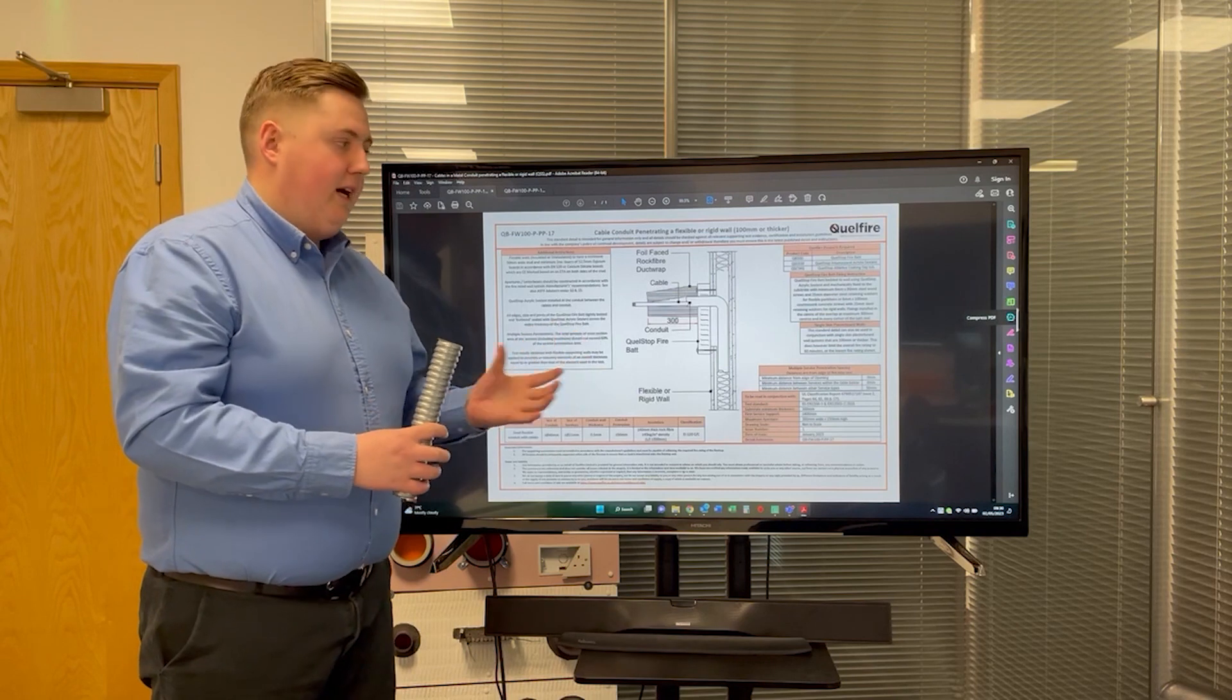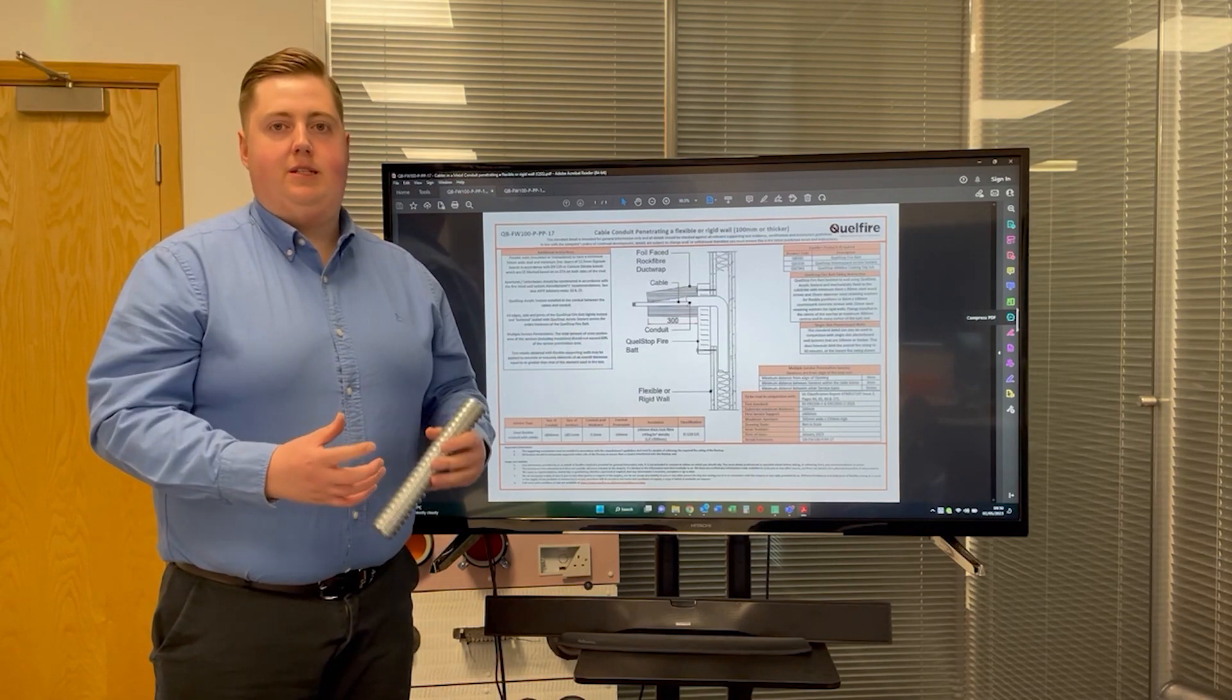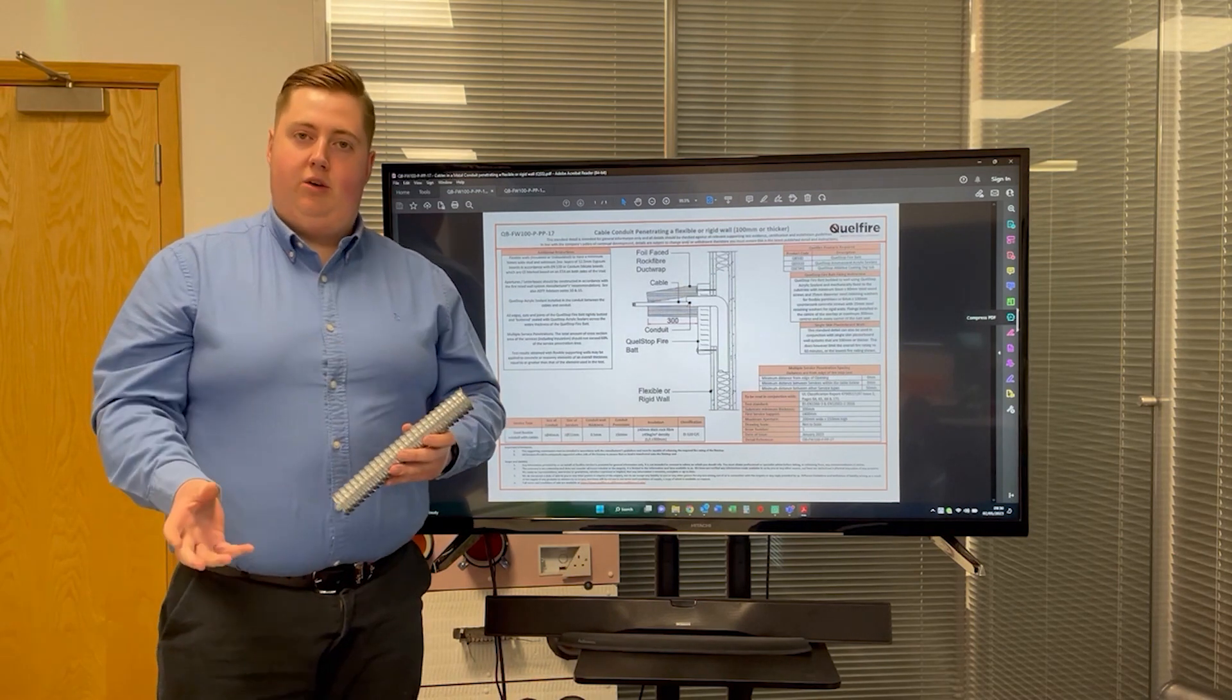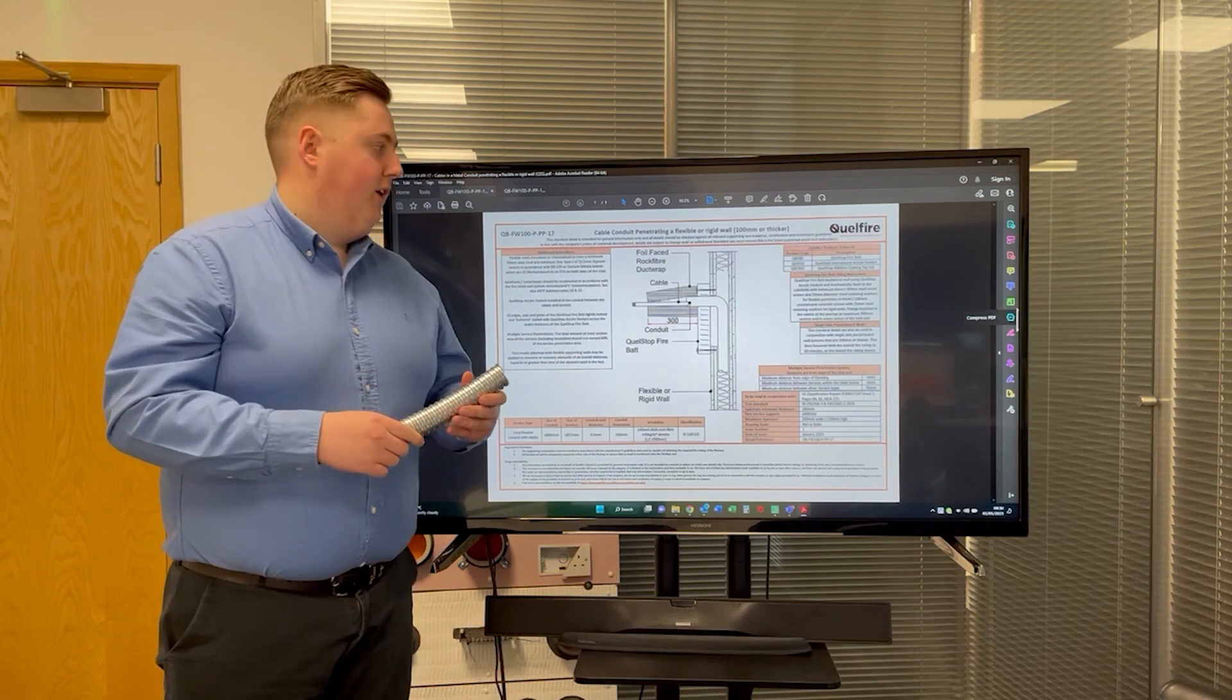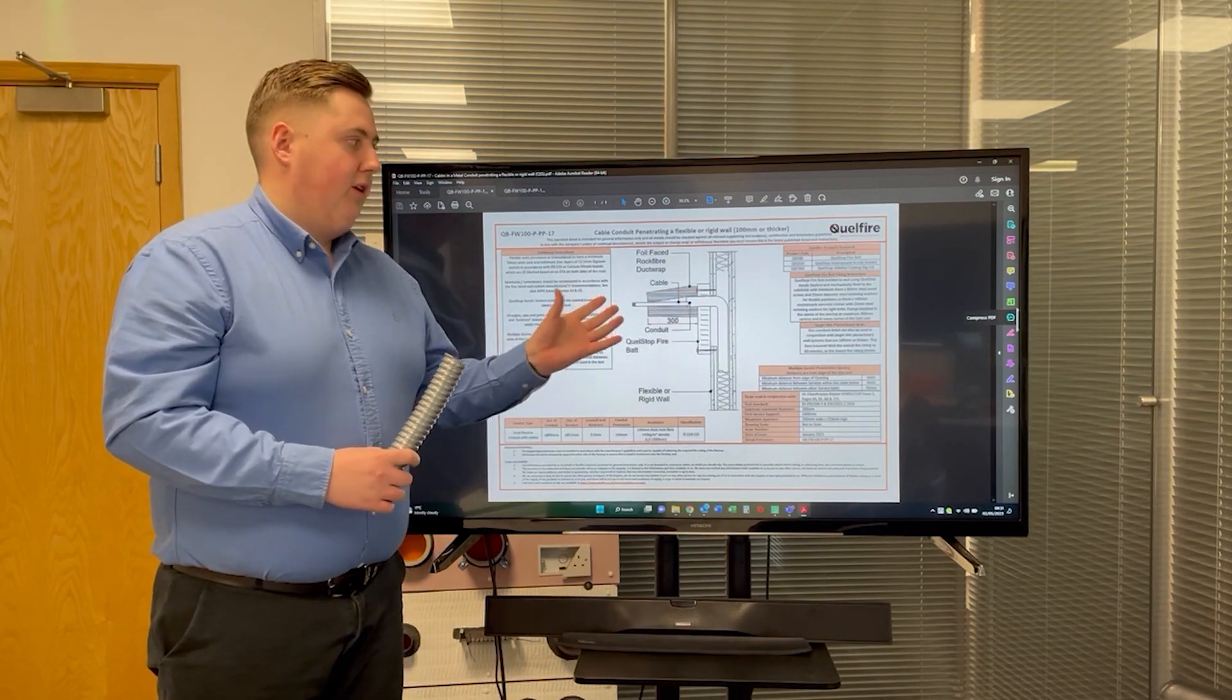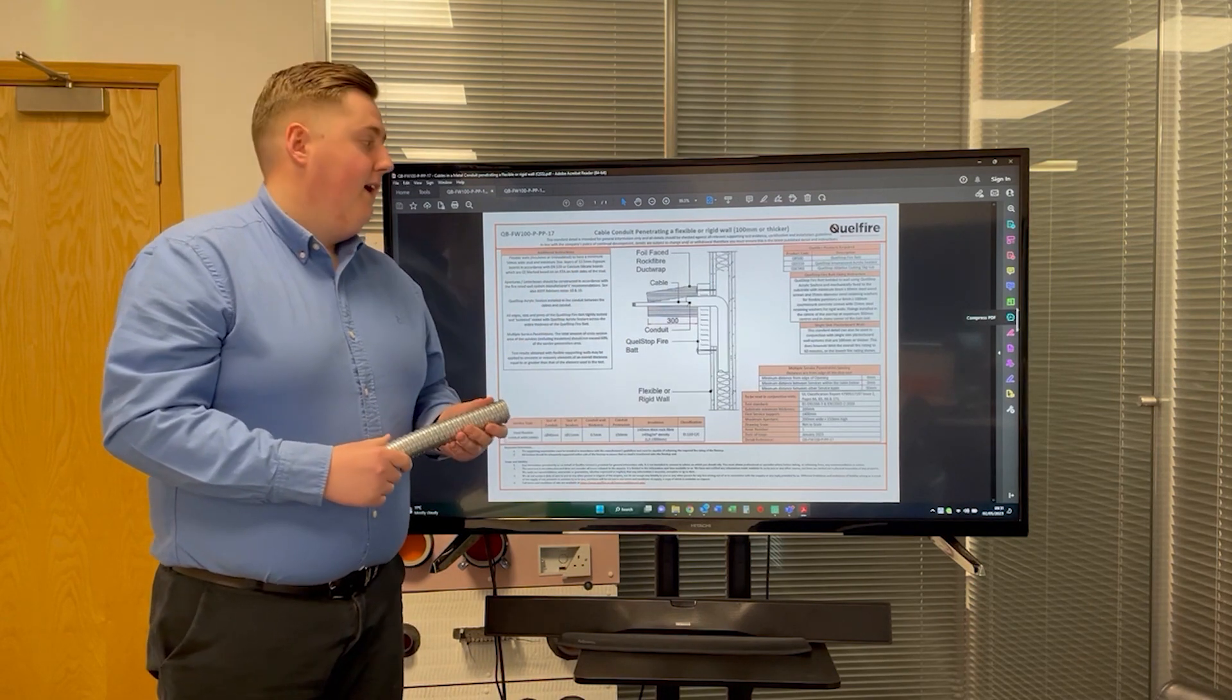The reason that is there is to increase the insulation rating of the seal. Obviously with it being a steel conduit as opposed to the plastic conduits we looked at before, it's a very good conductor of heat. There's a lot of heat transfer through this seal in the event of a fire, therefore it utilizes the rock fibre duct wrap around it.